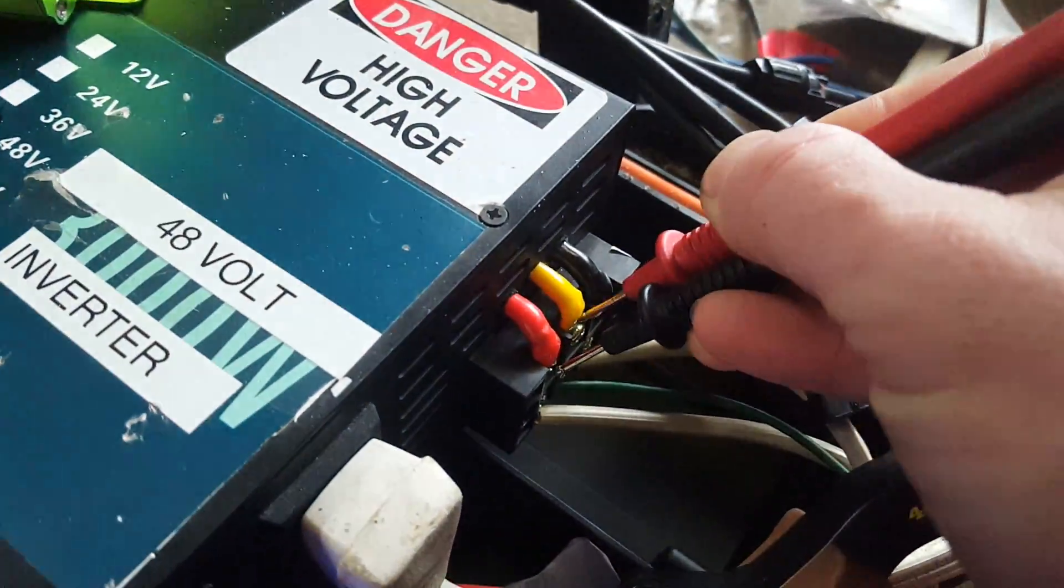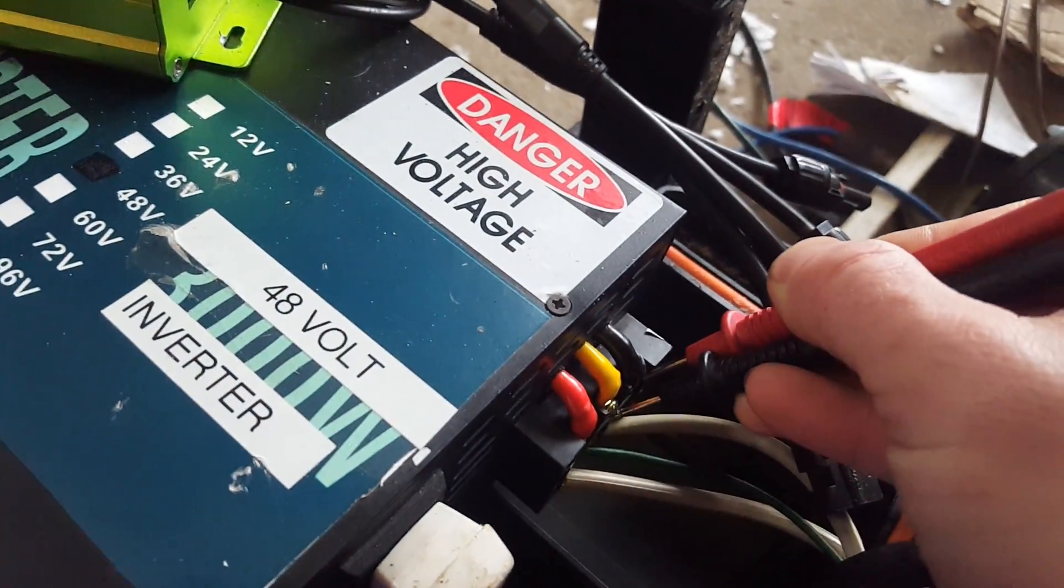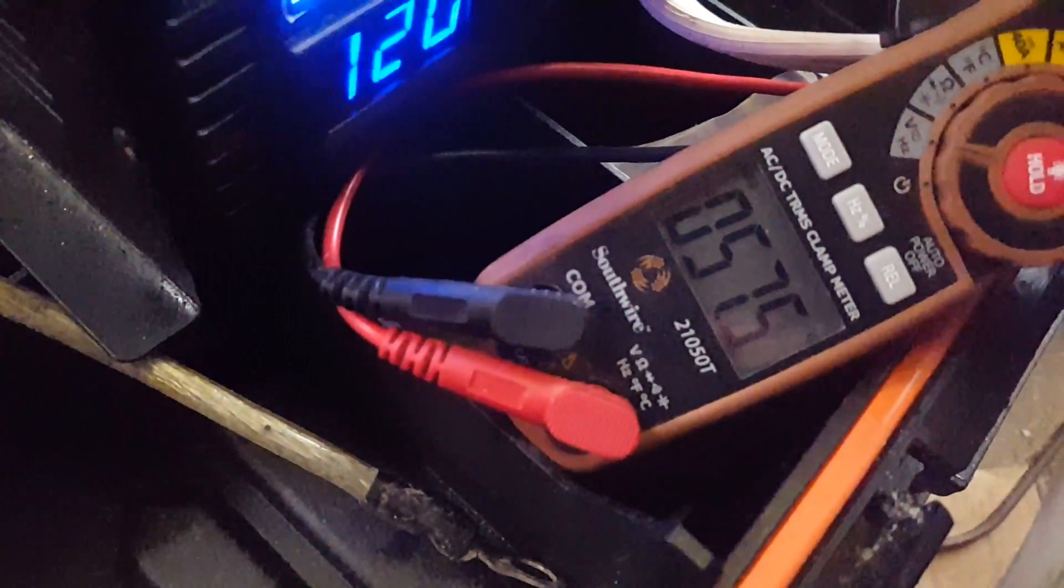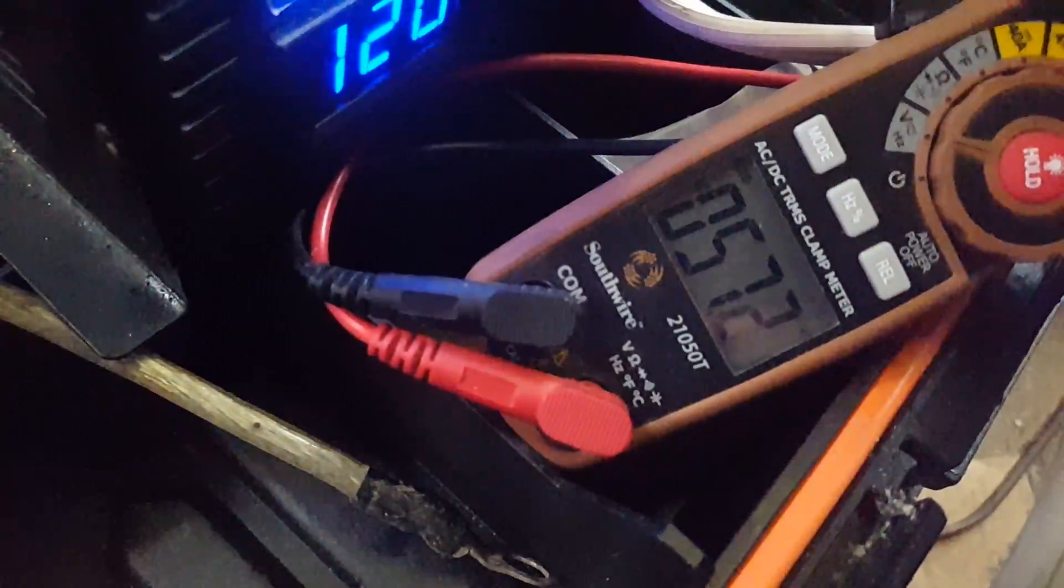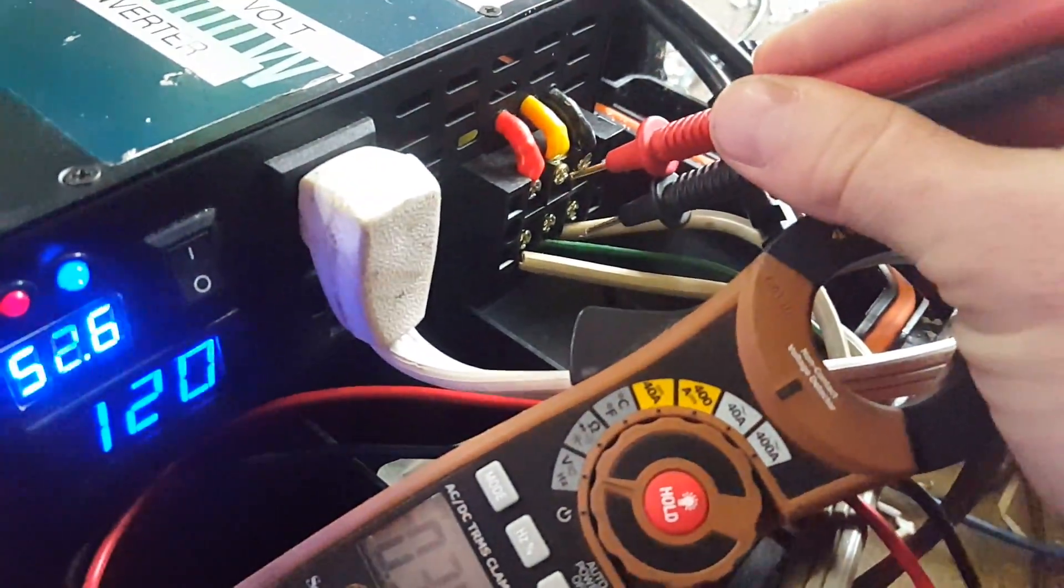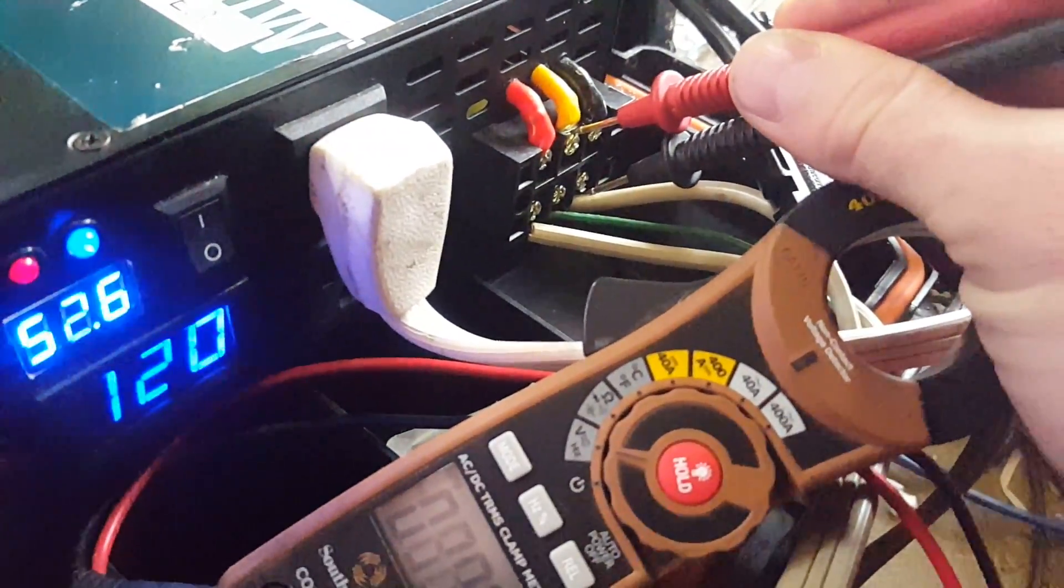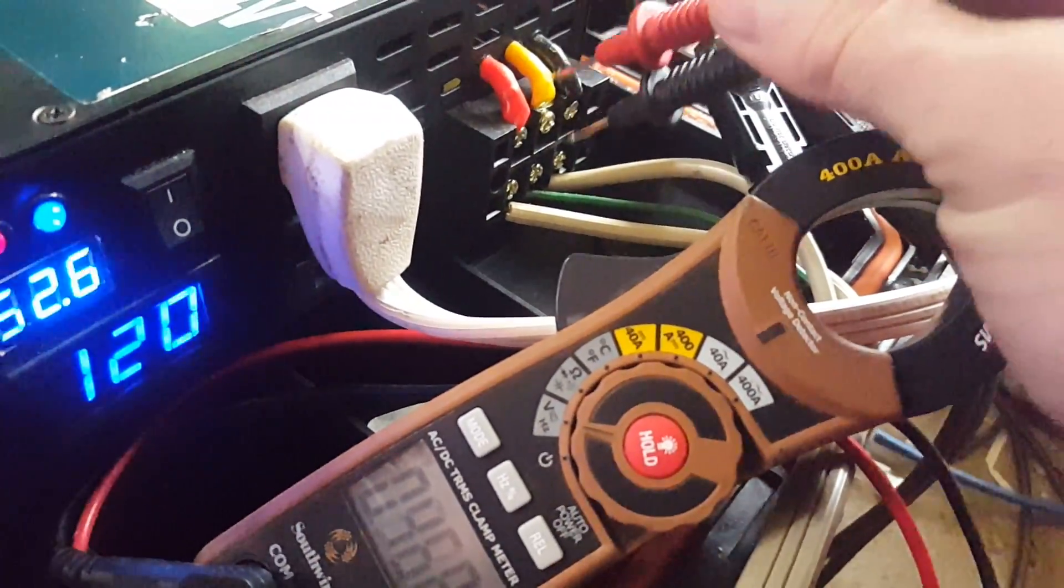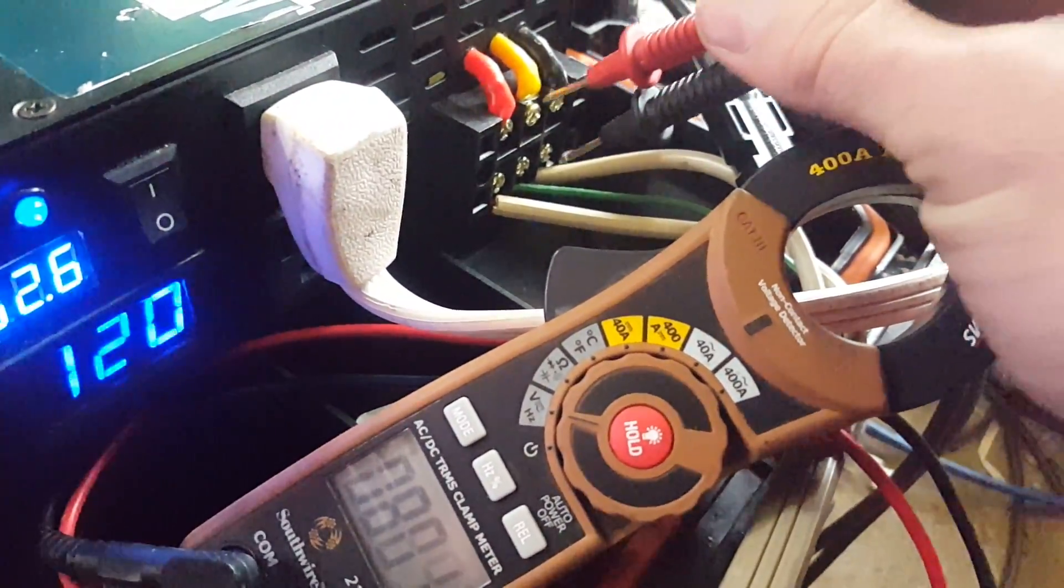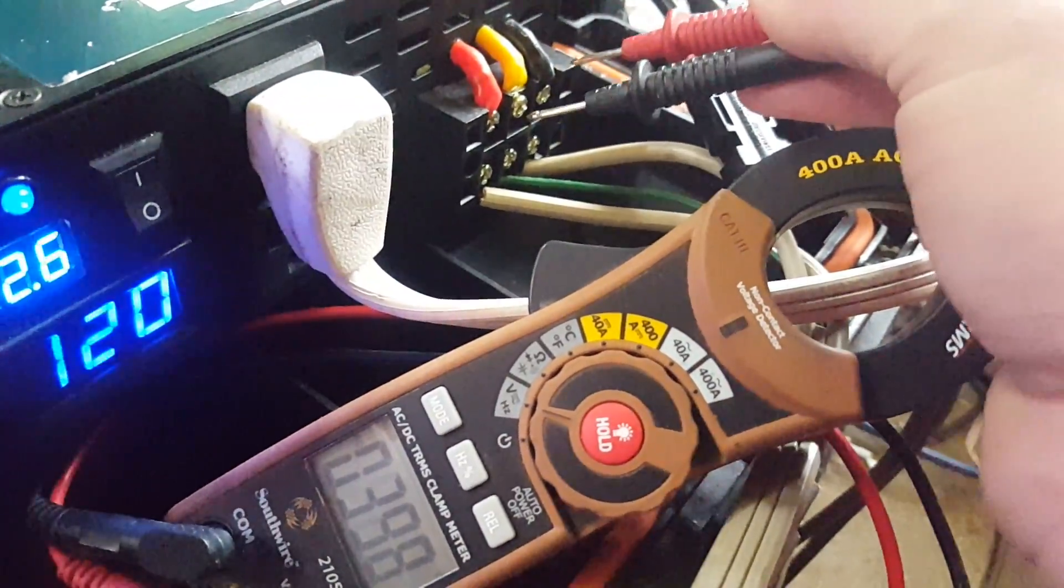Now, if I swap them, go from these two, I get 57 volts. So I get half power to this neutral, which is also bound to the ground. So in fact, you get a live ground from half power.